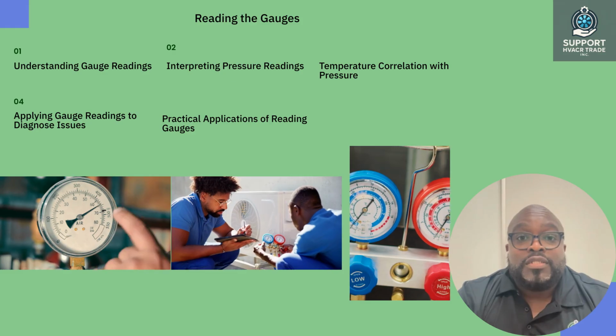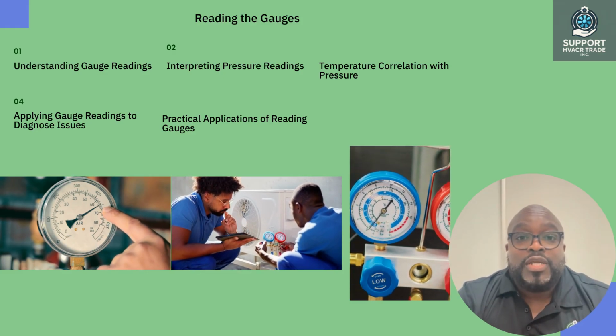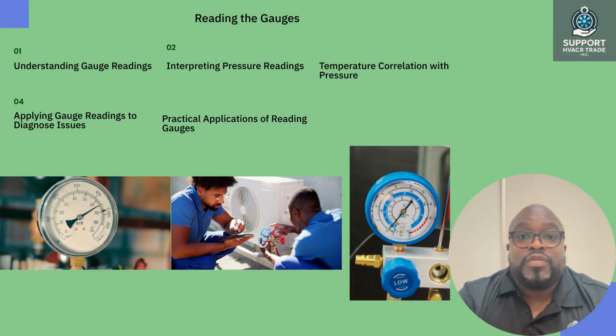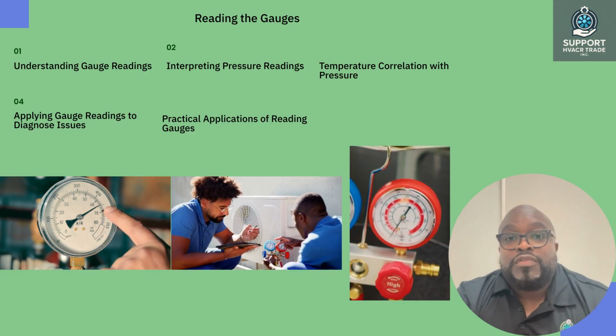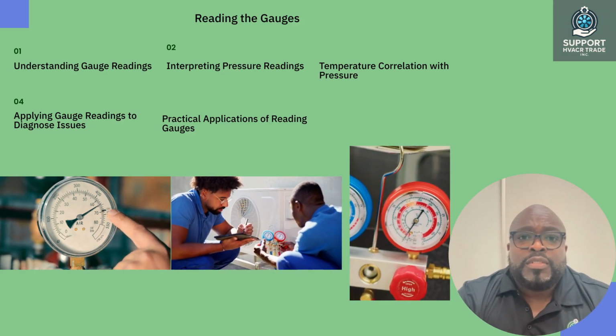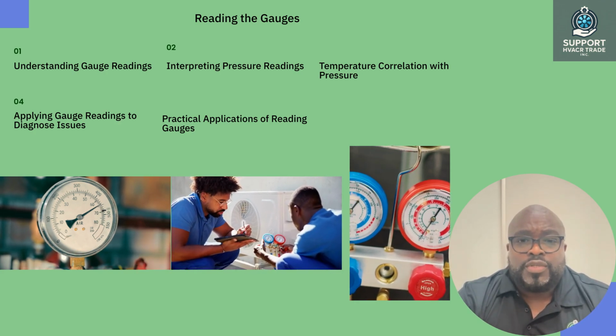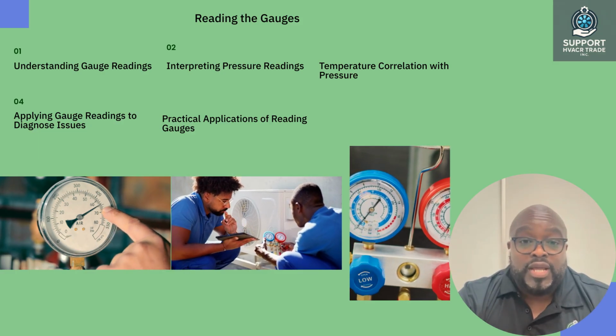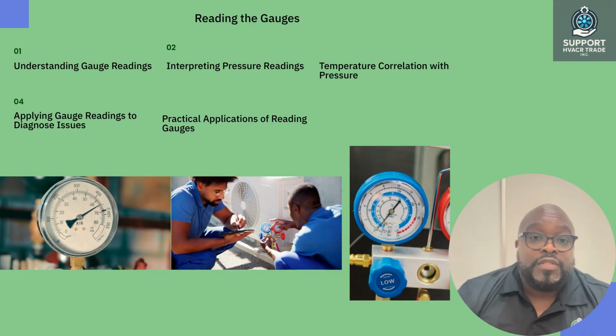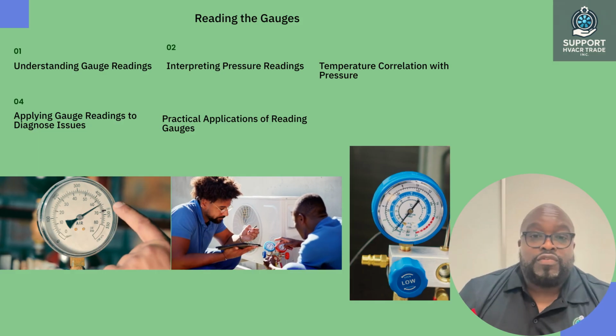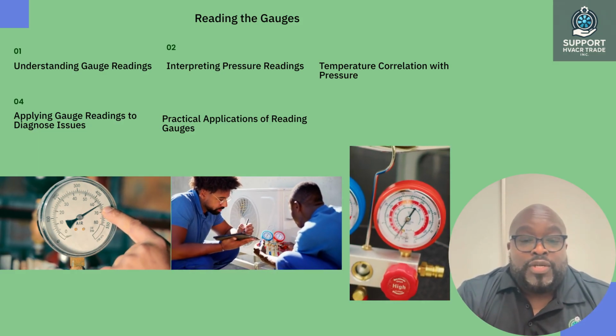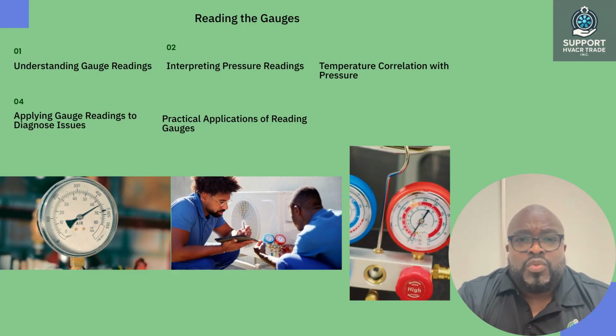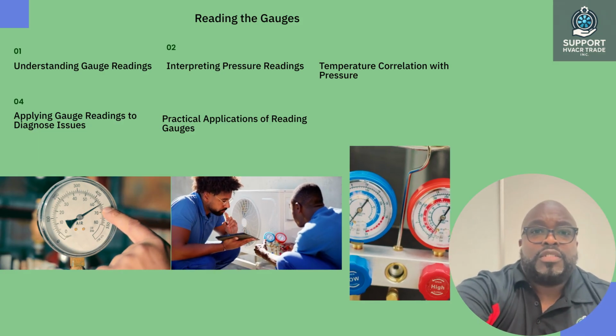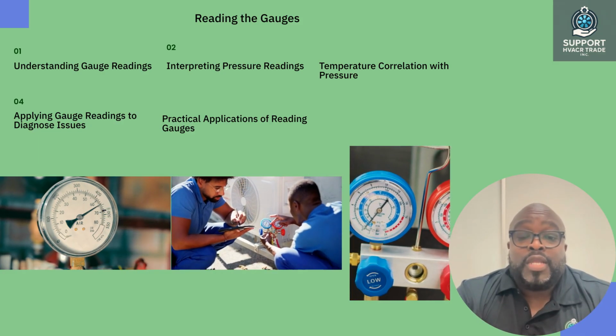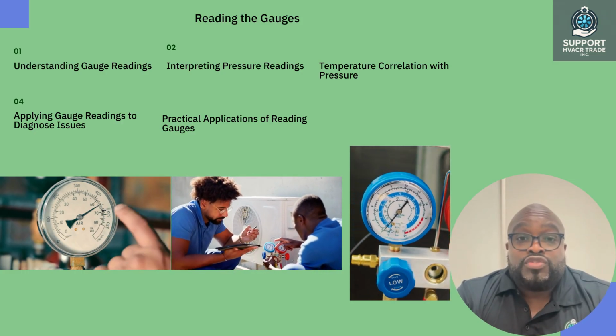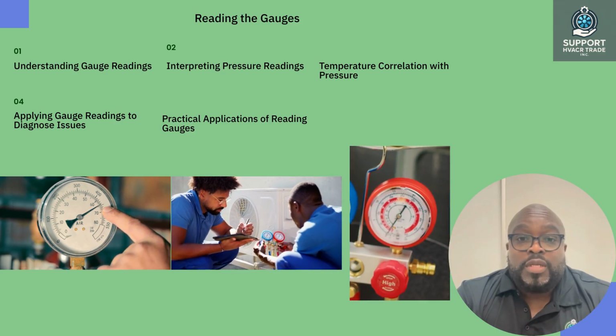The manifold gauge set consists of two primary gauges, the high-pressure gauge and the low-pressure gauge. Each gauge provides valuable information regarding the refrigerant state and the overall health of the HVAC system. Here's how to interpret these readings. High-pressure gauge: this gauge typically shows pressures from 0 to 500 psi. A higher reading indicates that the refrigerant is under significant pressure, which may suggest that the system is overcharged or experiencing a blockage. Low-pressure gauge: this gauge usually displays pressures from 0 to 100 psi. A low reading can indicate that the system is undercharged or there may be a refrigerant leak. In combination, these readings provide a snapshot of the refrigerant cycle and help assess whether the system is functioning optimally.